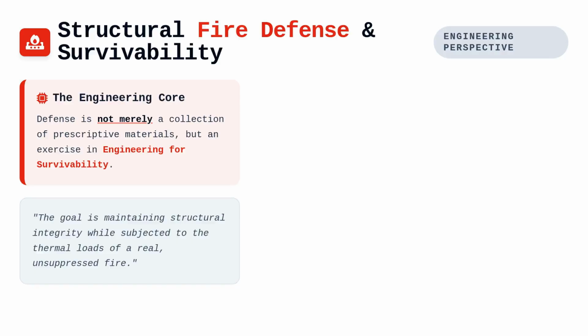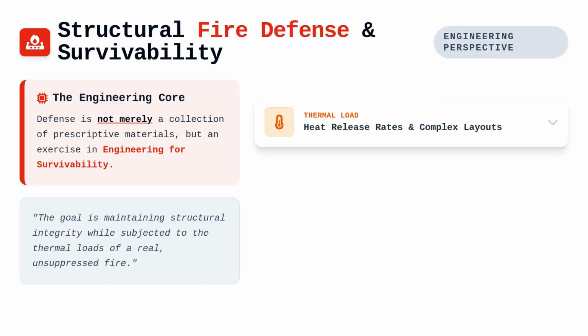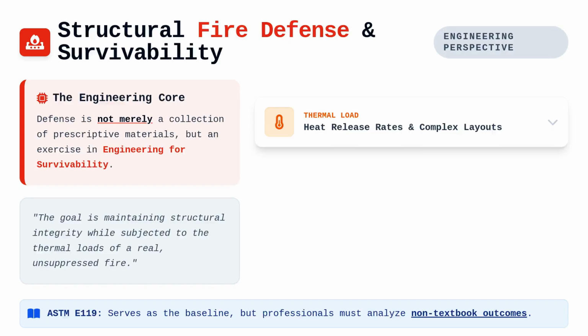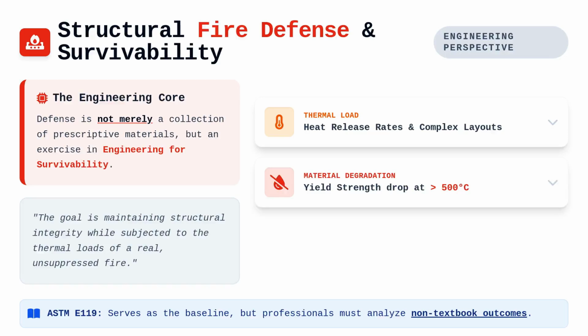When we discuss structural survivability, we are looking at the interaction between the fire's heat release rate, the thermal properties of the structural skeleton, and the mechanical response of load-bearing elements under high-temperature deformation. The code-prescriptive approach, relying on standardized furnace tests like ASTM E119, often serves as a baseline, but the advanced professional must grasp the thermomechanical behavior that occurs when a high occupant load or a complex layout prevents simple textbook outcomes.